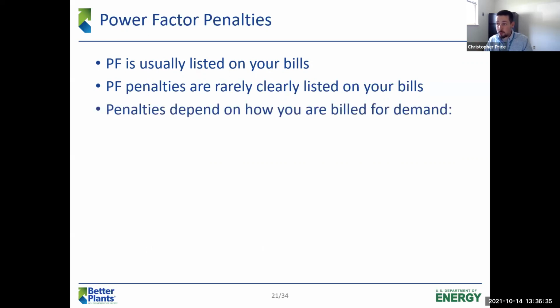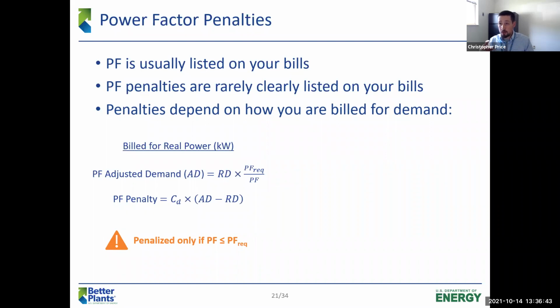How you're penalized for low power factor depends on how you're billed for that demand. If you are billed based on real power, so you'll know this if your demand charges are calculated by kilowatts, your utility will have a minimum required power factor, and that's usually 0.9 to 0.95, somewhere in that range. You can calculate your adjusted demand, power factor adjusted demand, by multiplying your real demand by the ratio of the required power factor to your actual power factor. And the demand penalty for having a low power factor is just your cost of demand multiplied by that difference between the adjusted and real demand. Important here is that you are only penalized for a power factor that's less than the required power factor. So if you were correcting it, you would only correct it up to that minimum required. You would never try and get it up to 1.